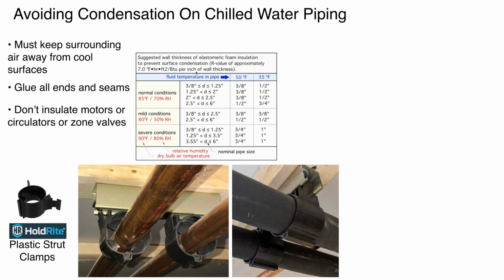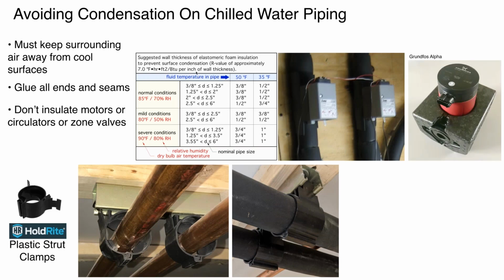So it's a lot better than trying to insulate the pipe and then just put some kind of a simple hanger underneath it. Over time, the insulation will sag on the hanger. It doesn't look very good. This is a system that prevents that sag. If you're insulating around zone valves, don't insulate the actuator. You see the valve body is insulated here.